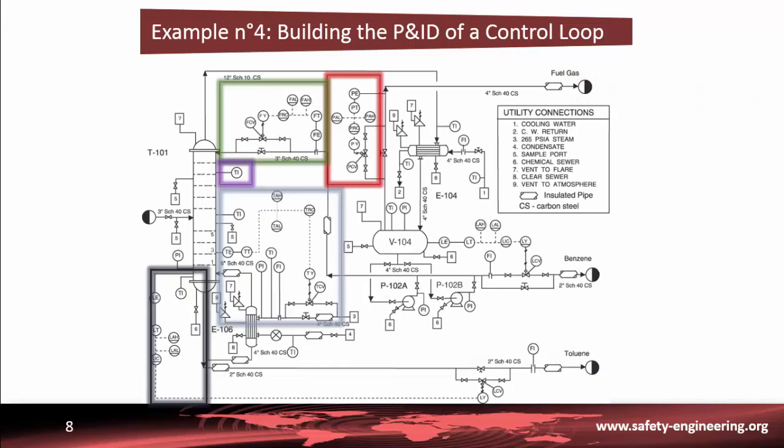The other control loops are structured in exactly the same way. You can see here a control loop for the pressure into the vessel. The measured variable is the pressure at the outlet of the drum and the manipulated variable is the outlet flow at the top of the drum. Both alarms are PAL and PAH.